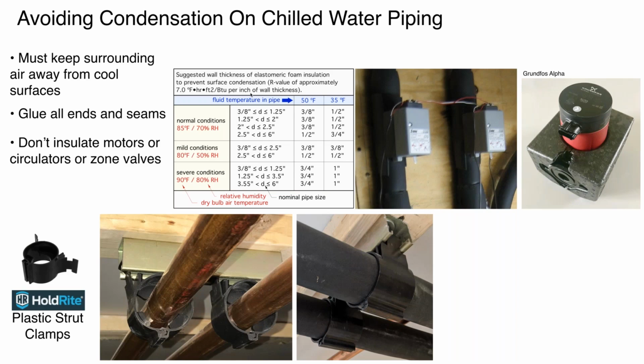One of the things I will stress, it is not sufficient just to put the shell and just push the two halves together. You need to seal it up completely with either foam tape or caulk. You cannot let surrounding air get inside that shell and get to that volute. If it does, it's going to cause condensation. So we'd love to see more insulation shell products on the market, not only for circulators, but for isolation valves or other components, so that it's easier for an installer to create a good monolithic insulation system on their piping.